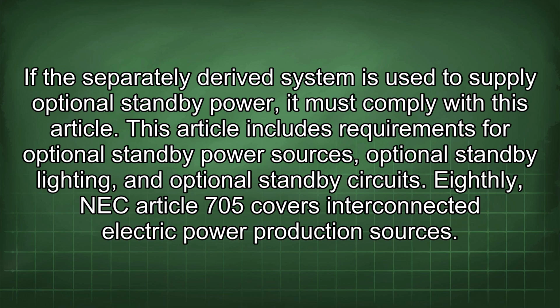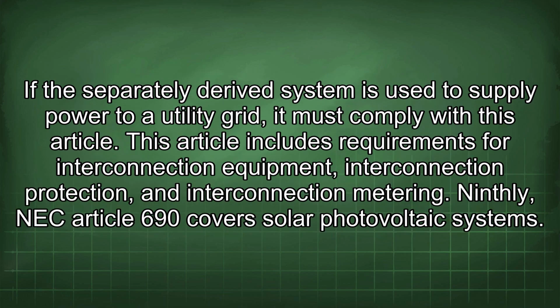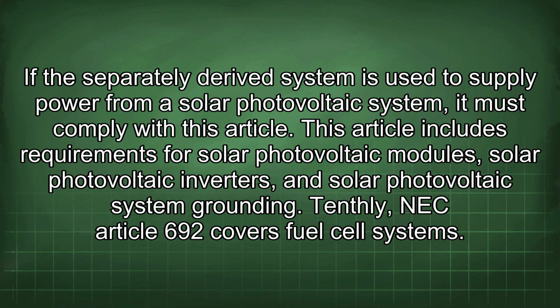Eighthly, NEC Article 705 covers interconnected electric power production sources. If the separately derived system is used to supply power to a utility grid, it must comply with this article. This article includes requirements for interconnection equipment, interconnection protection, and interconnection metering. Ninthly, NEC Article 690 covers solar photovoltaic systems. If the separately derived system is used to supply power from a solar photovoltaic system, it must comply with this article. This article includes requirements for solar photovoltaic modules, solar photovoltaic inverters, and solar photovoltaic system grounding.